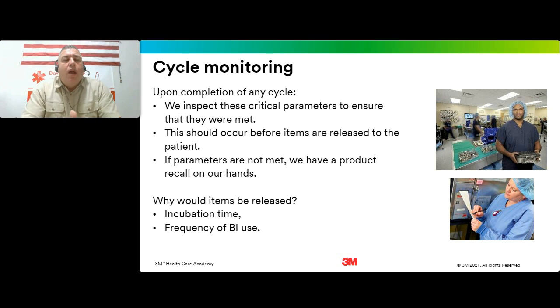Now you say, well, why would items be released? Well, items are released because the incubation time is there for the biological test. And how frequently are you running your BI? You want to make sure that you're meeting those guidelines for incubation. A lot of times I'll come in and see the tests are run using a super rapid BI readout that only reads in less than 25 minutes.